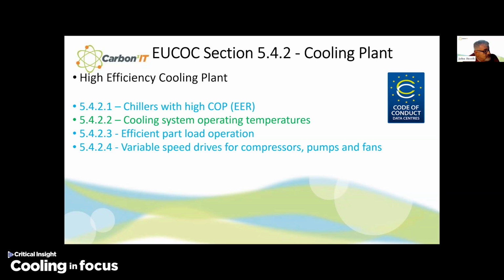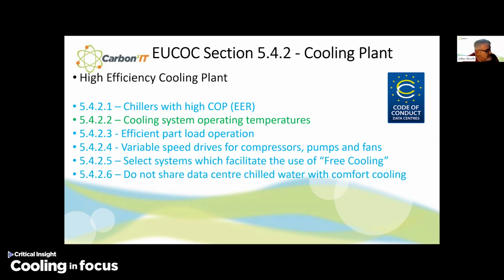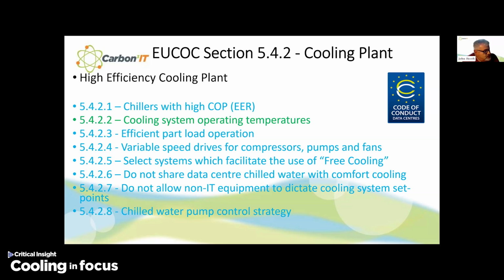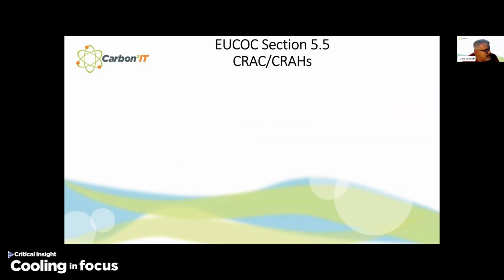Variable speed drives for compressors, pumps, and fans. And to be honest, it's almost impossible not to get variable speed drives for air conditioning equipment at the moment. Select systems which facilitate the use of free cooling. Don't share your data center chilled water with comfort cooling. And do not allow non-IT equipment to dictate cooling system set points. And then have a chilled water pump control strategy.